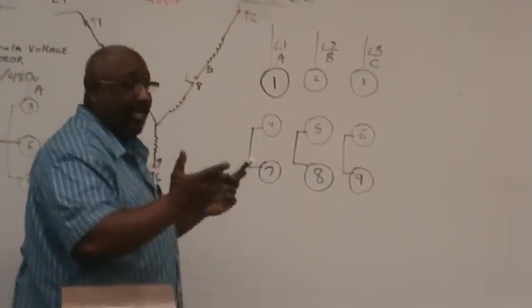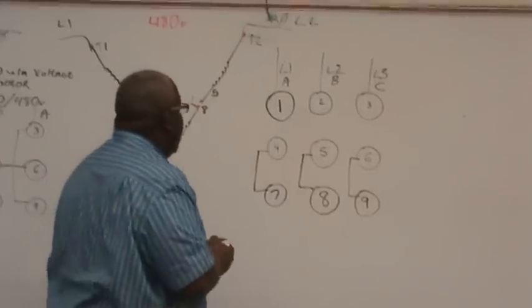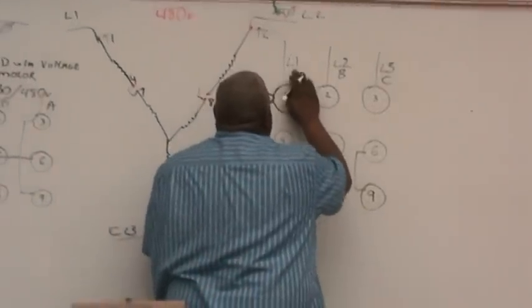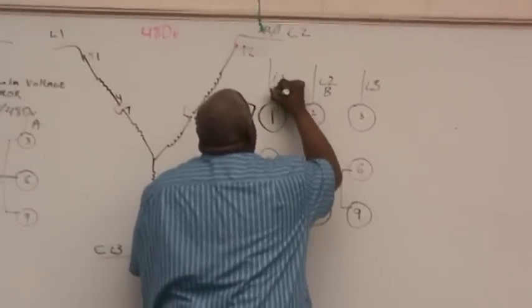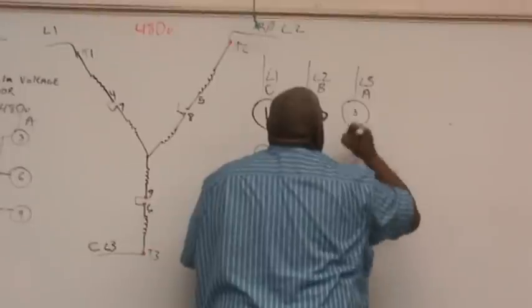Again, if I need to reverse the rotation, just take the two leads of A and C and swap. Make this C, and make this A.